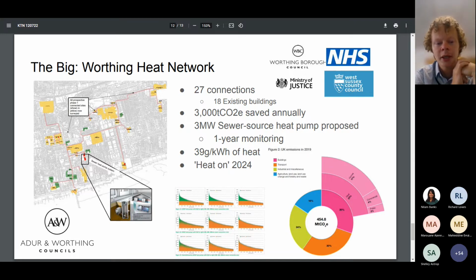The primary proposed heat source for this heat network is a 3 megawatt system, so 1,000 times bigger than the original Kensa ones we showed earlier in the programme. It's a sewer source heat pump, an in-sewer system rather than being located at a wastewater treatment works.